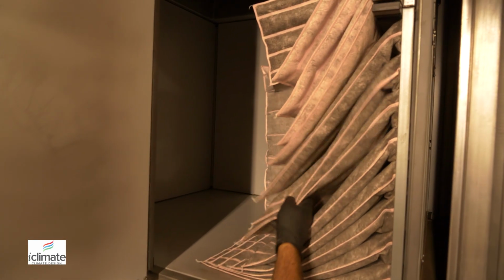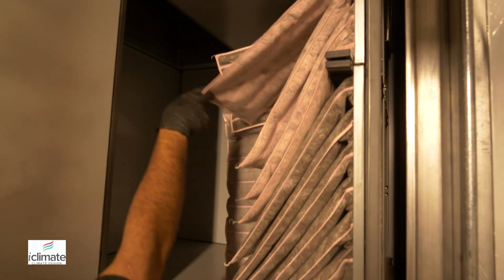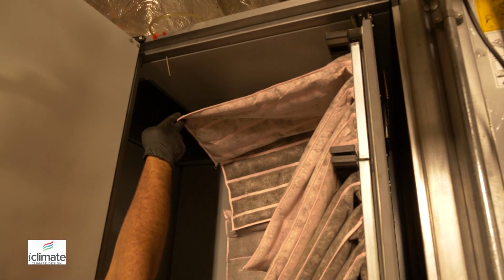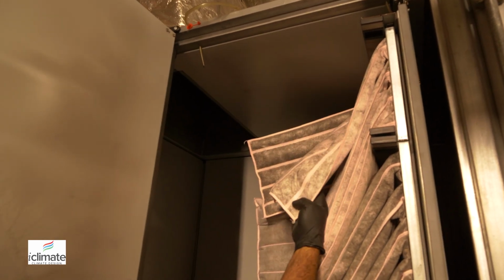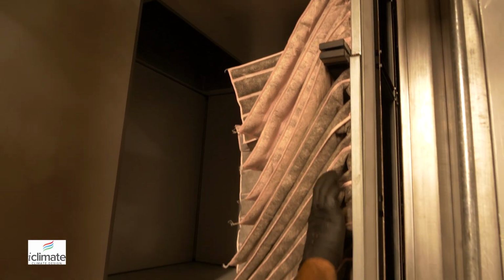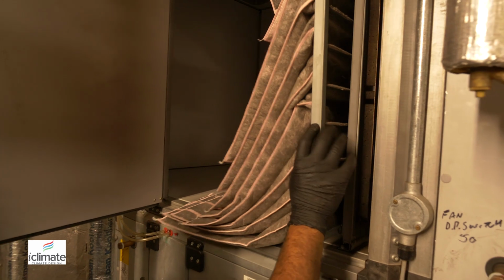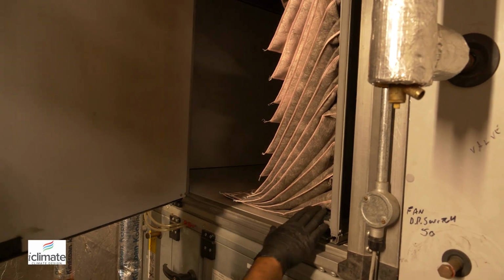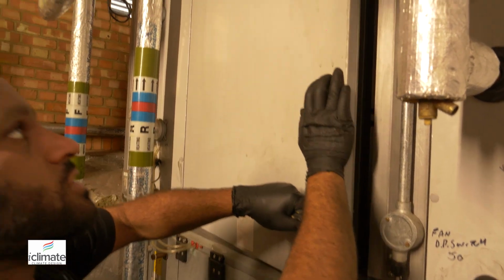And these are the bag filters. So these are the filters that when the air blows through, they sit in that orientation, and the air comes into this pocket and is filtered. So these are critical to maintain. They pull out like this, and they go back in, and we change them on air handlers annually, depending on the usage.